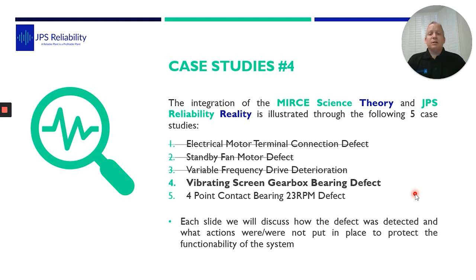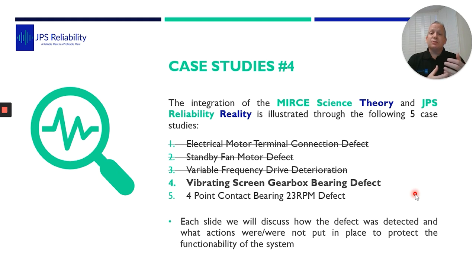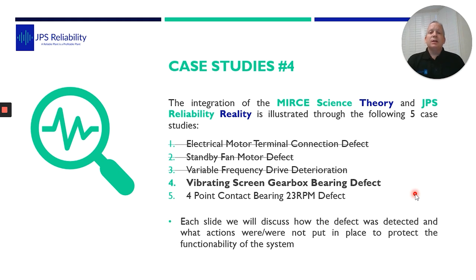If you would like to view the other three, please go to the RMS website and there will be links there. The first one was an electrical motor connection defect, where we picked up a defect on the motor through vibration analysis — also highlighting the need to use other technologies like thermography. The second case study was on a fan motor bearing where transferred vibration from another running asset caused a failure. The third was a very interesting one on a variable frequency drive defect on the IGBT card. And today we're going through a vibrating screen gearbox bearing defect.